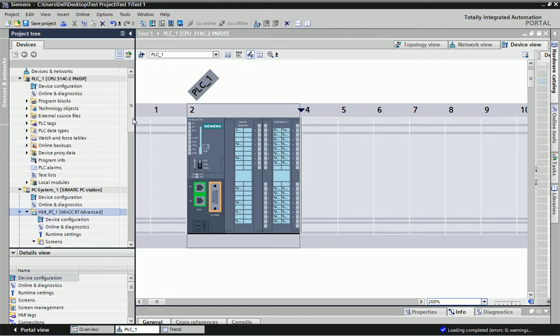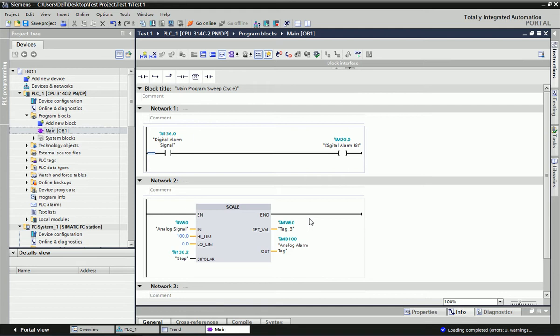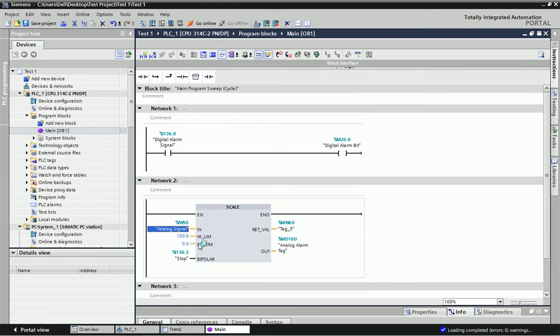Before going directly to the SCADA, we will look at the programming block. I have taken an analog signal coming from the field area. You can see I have taken a scale block — the analog signal address is IW60. I have made scaling from this analog signal so I will get the analog signal in MD100 within the scaling range of 0 to 100. We will see the trend from this MD100 tag.